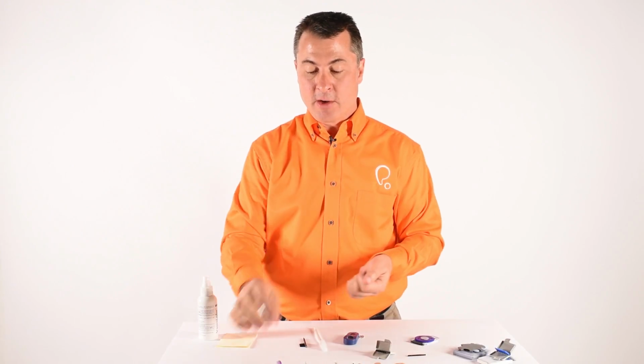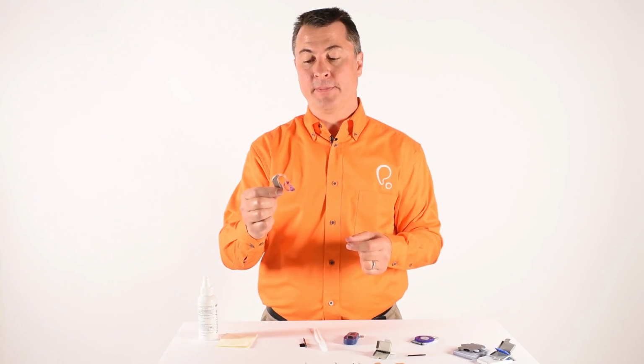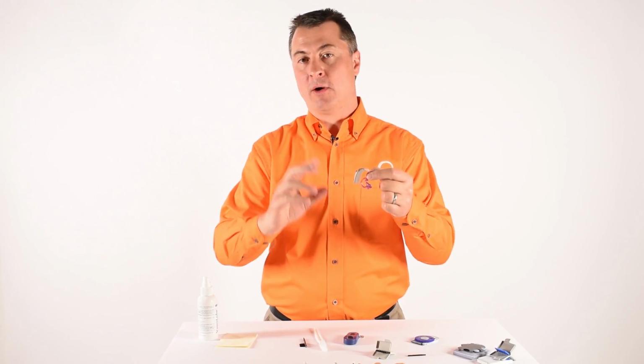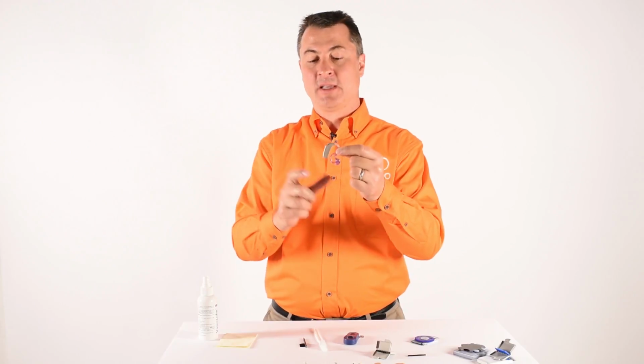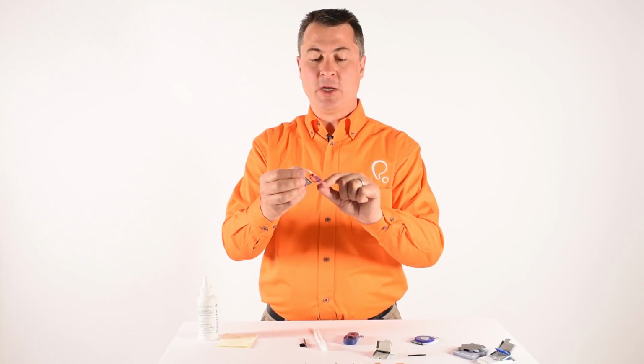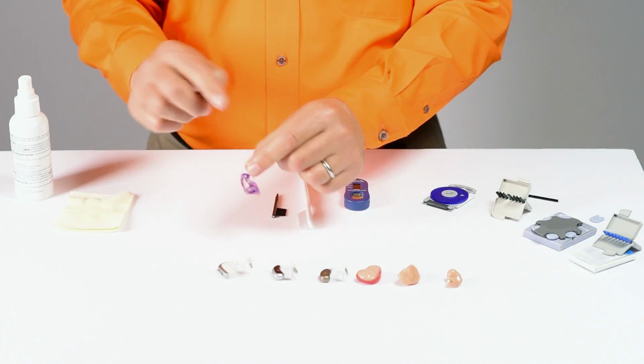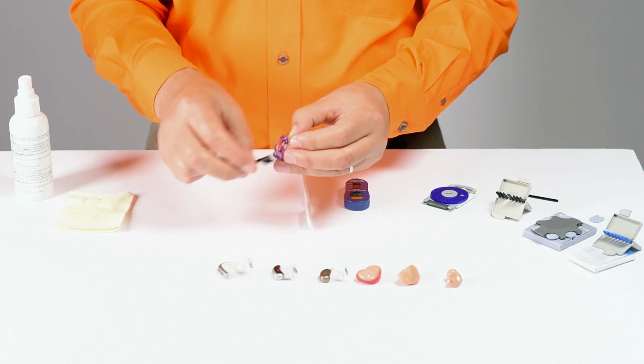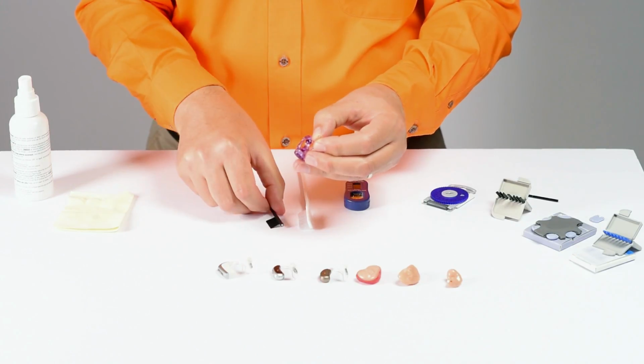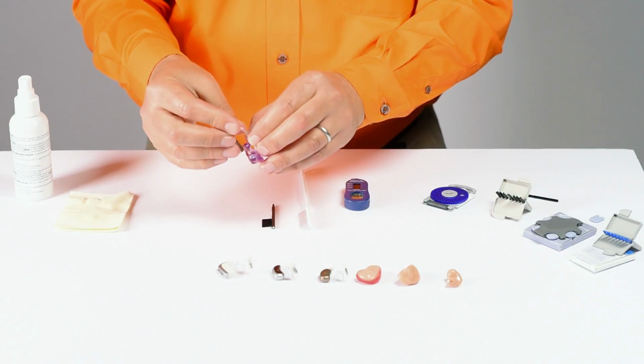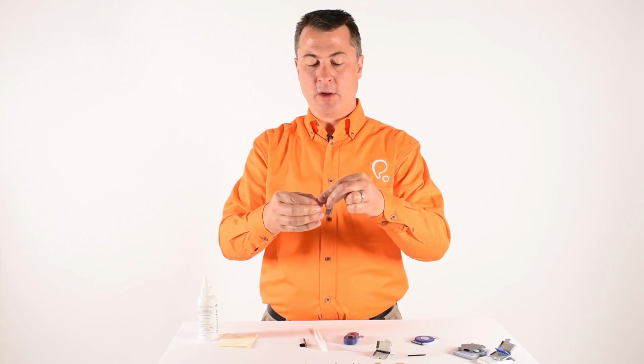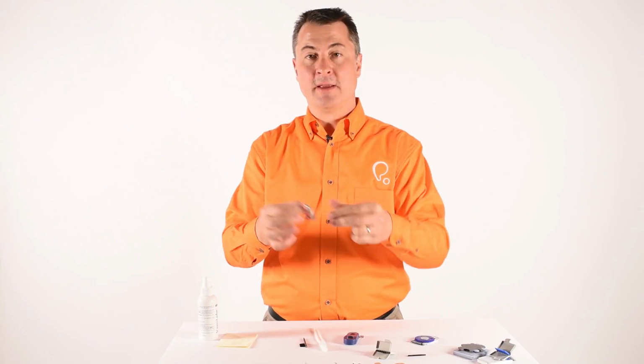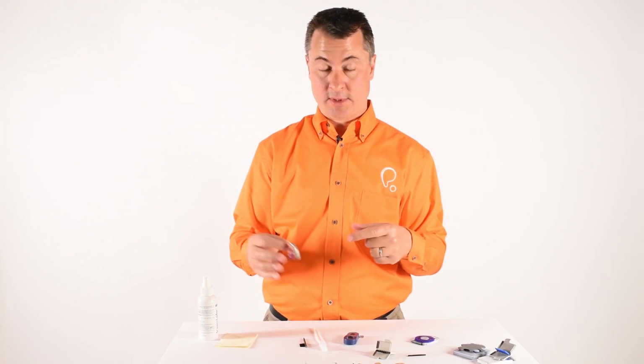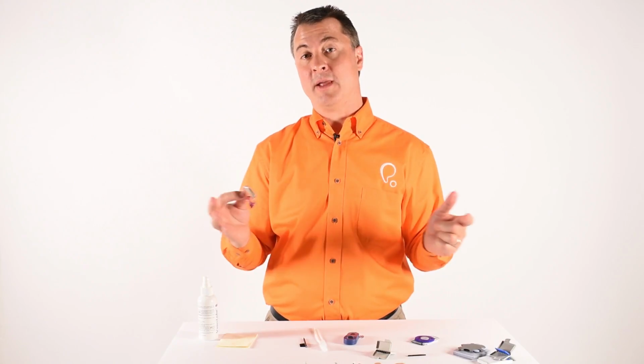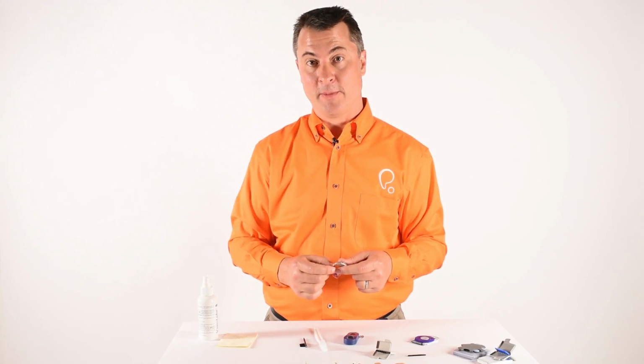The last case involves much larger hearing aids that usually pack a lot more power. Many people might call this old style, but we have some very sophisticated ones like this. This one has an earpiece that you can take apart, and you would have to clean in here, or you can run some water through to get any blockages away. You make sure it's dry, you reconnect it, and there you go, you're back in business. And that is how you double check, or take some of the steps, to solve your problem if your hearing aid stops working. Thanks very much.